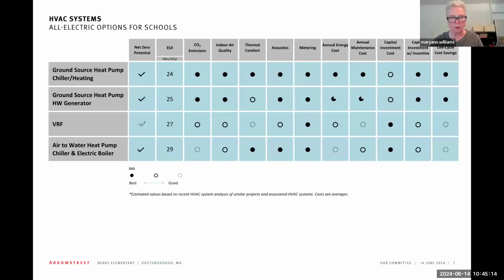Kate, how does this chart relate to whether it's a new option versus a renovation option? You could assume it's essentially the same. When it's a renovation option, the biggest cost implications are ductwork, and ductwork is the same between all of them. You're running refrigerant lines for VRF versus potentially piping lines for the ground source. So it should be fairly similar, and all the other metrics are the same. The construction cost would be the only one that might fluctuate a little bit. I apologize that I can't remember exactly what the distribution system is in the existing Neary building. It's probably unit ventilators, perimeter heat, and H&V units for makeup air. That's pretty much it, like a typical school.